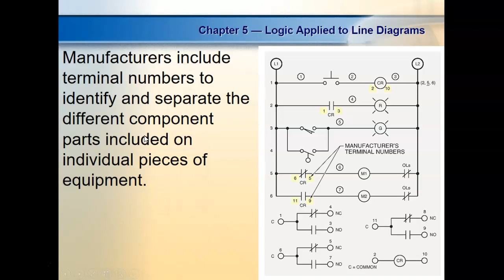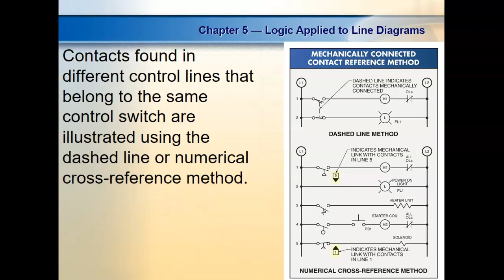Contacts found in different control lines that belong to the same control switch are illustrated using dashed lines or numerical cross-reference. So the dashed line saying, hey, if one's closed, the other's open, can be used. You can also have these little reference numbers. When one's energized, the other de-energizes.